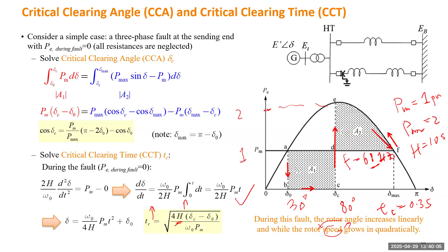The generator inertia. The higher the inertia, the slower the rate of change in angle. Based on our calculation for the critical clearing angle, if inertia increases, the critical clearing time will increase. A bigger critical clearing time means you have more room to do the control to prevent the transient instability.